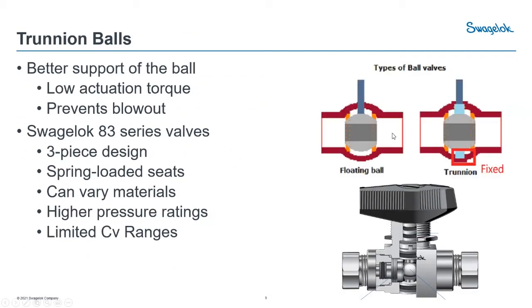There are really two types of ball designs: floating ball and trunnion ball. With a floating ball, it's supported only on the top. A trunnion ball is shaped like a spool piece with a bushing on top and bottom, supporting the ball on both sides. This actually lowers your actuation torque and can prevent blowout if you're concerned about overpressurization — because it's fixed in two spots, it resists pressure surges.